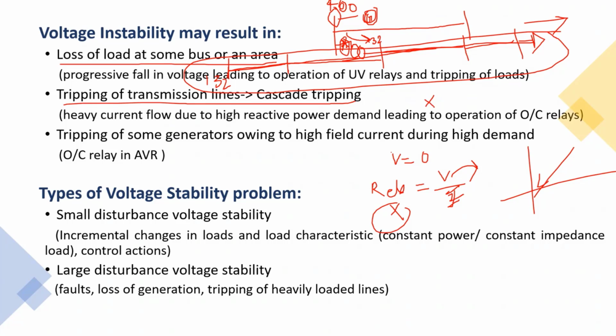Why? The impedance was very, very high. So with very high impedance, if you want to transfer that much power and there is no reactive support, on a very long 132 kV line, then you know that P = V1 V2 / X * sin delta, right? If you have, let us say, 1 per unit, X is very high, what will happen to this V2 if you try to push that much power? Somewhere this V2 will go to zero. So this is what voltage collapse will look like.